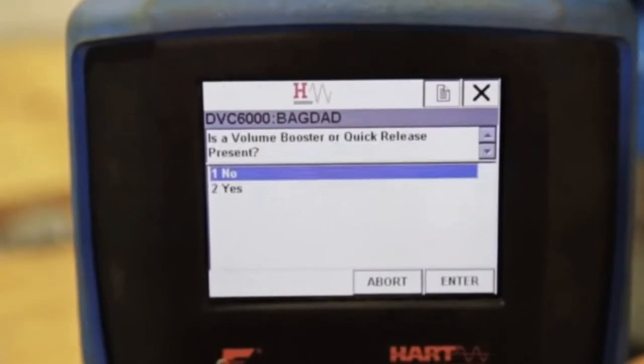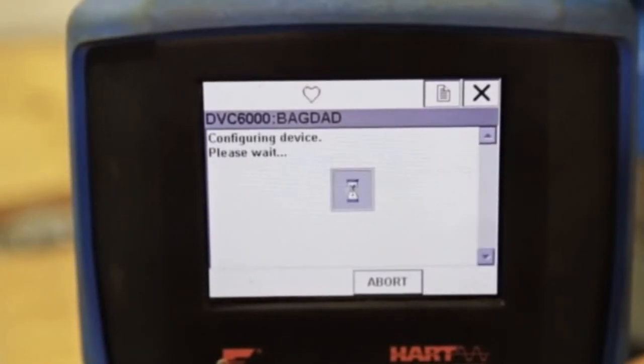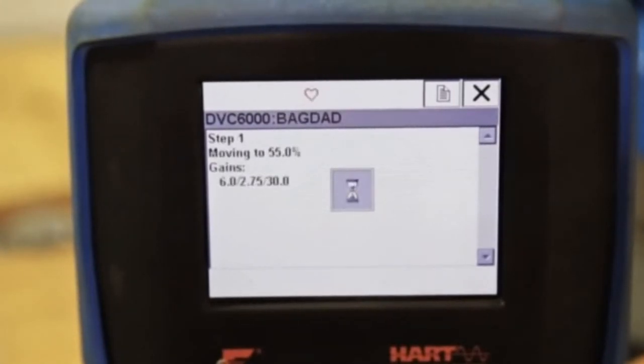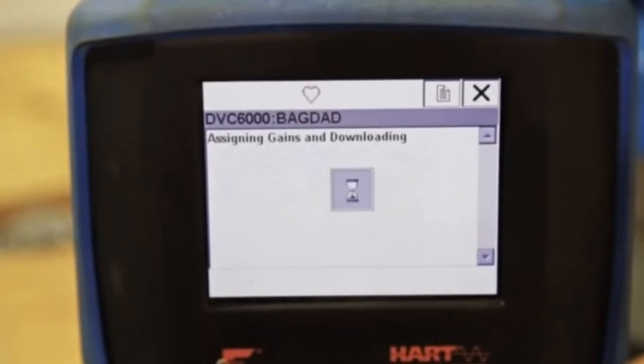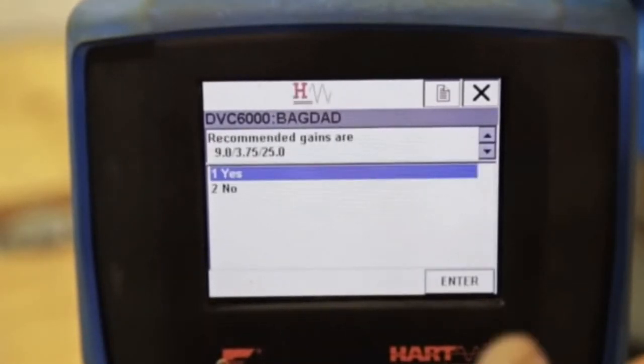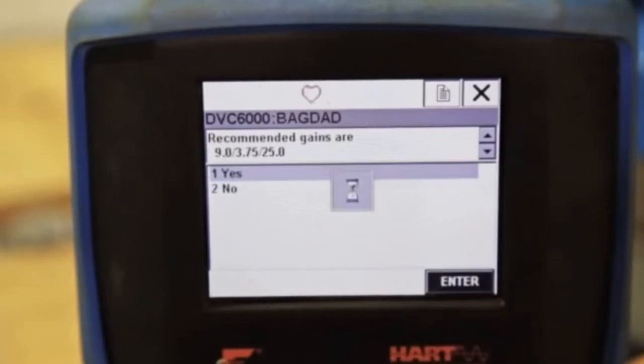Here we will select No again since we don't have a volume booster or quick release on this actuator. And No for graphite packing as well. Wait while the device is configured and steady state conditions are checked. Accept the recommended gains.